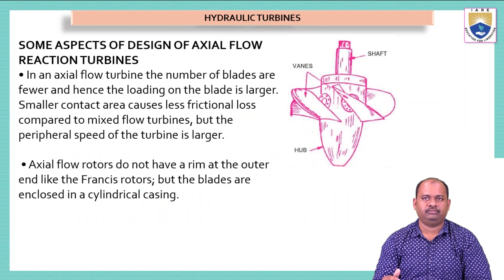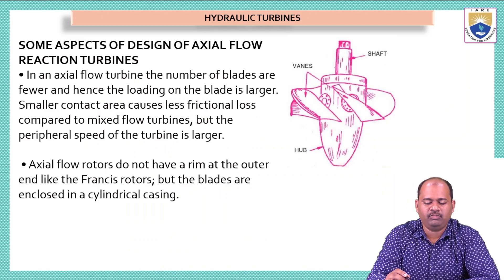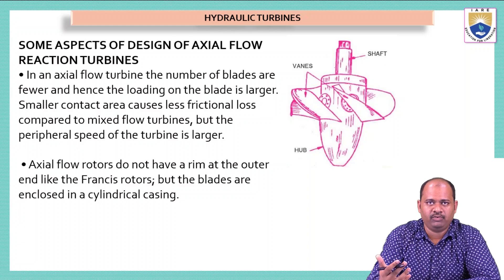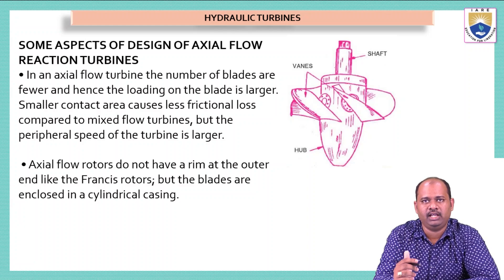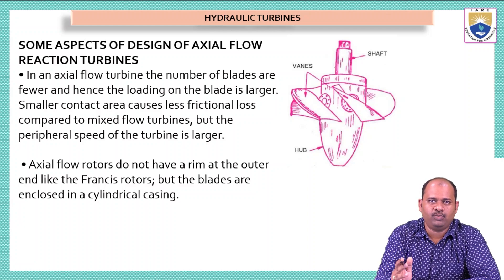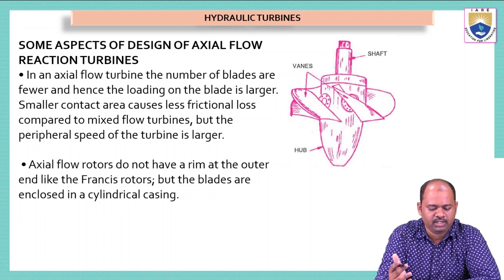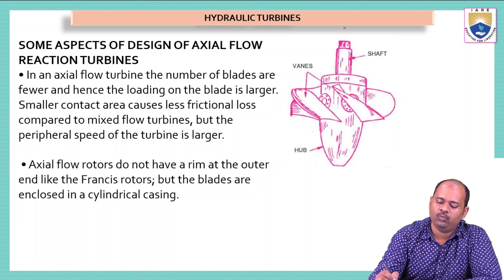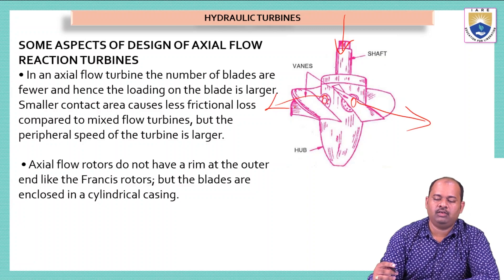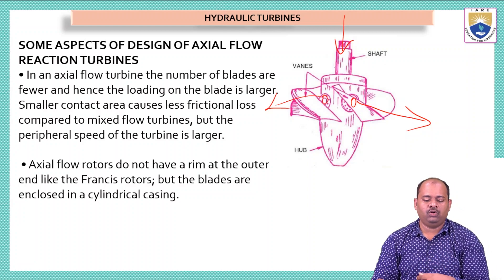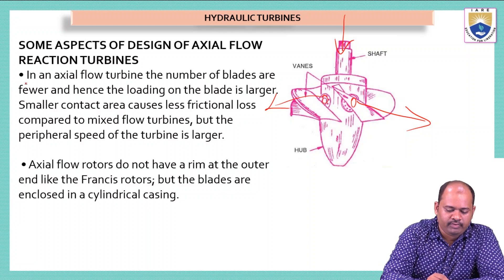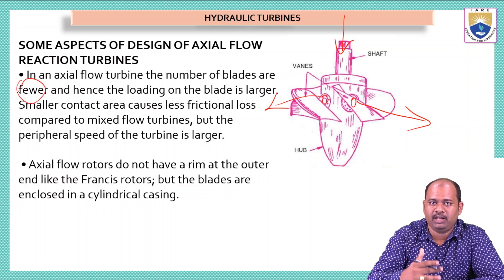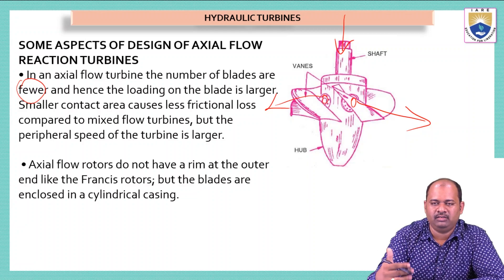In the Francis turbine, water enters in the radial direction and exits from the center of the shaft in the axial direction. In the axial flow turbine the number of blades is fewer, hence the loading on each blade is larger. Smaller contact area causes less frictional losses compared to mixed flow turbines, but the peripheral speed of the turbine is large. The fewer blades are kept because the flow of water acts in a specific direction, and a small amount of water can make the turbine rotate.